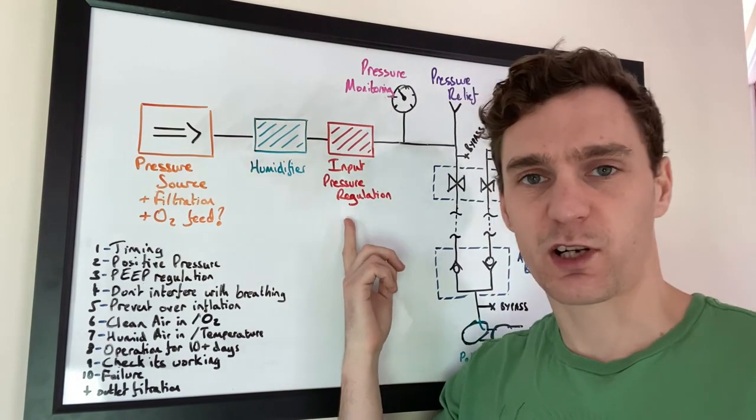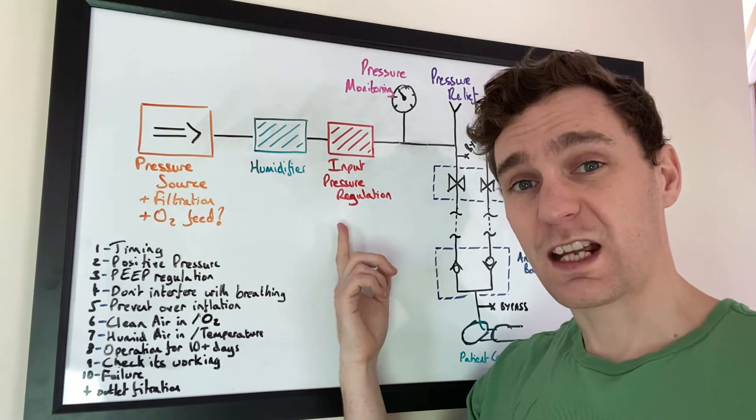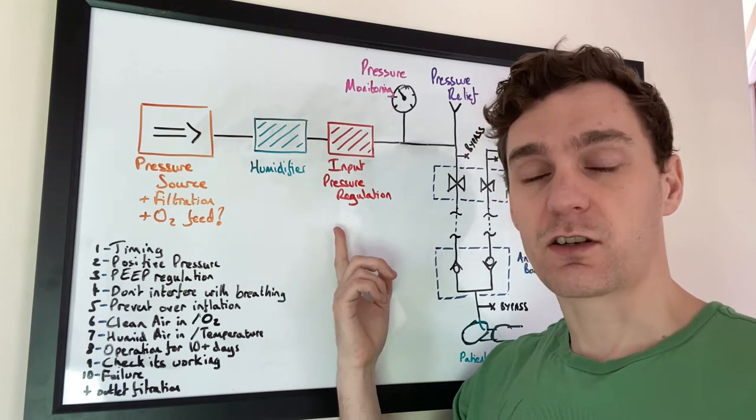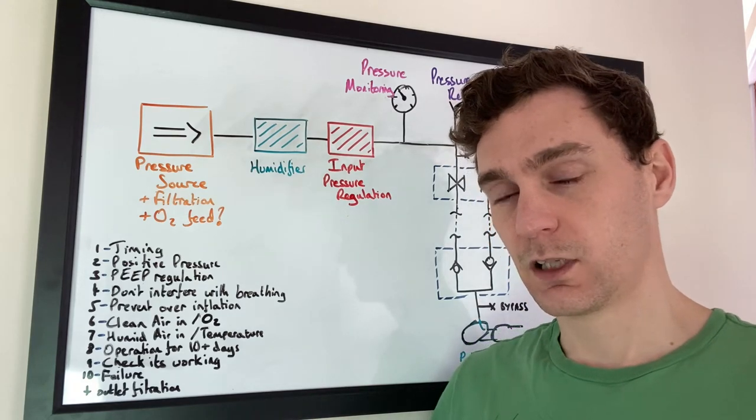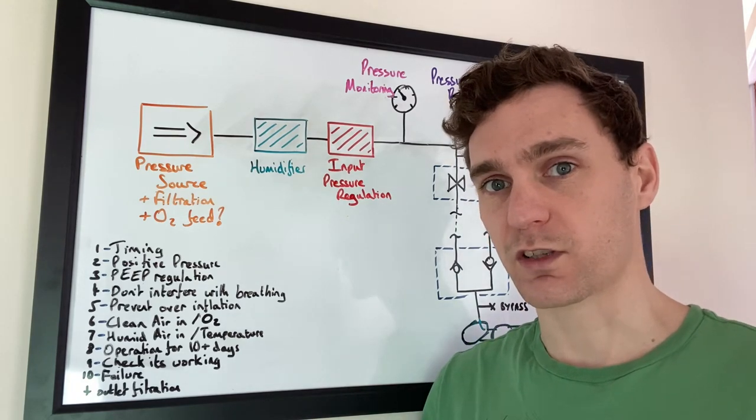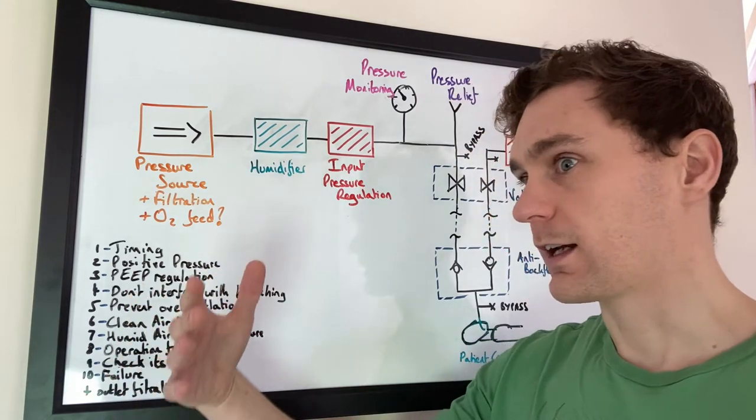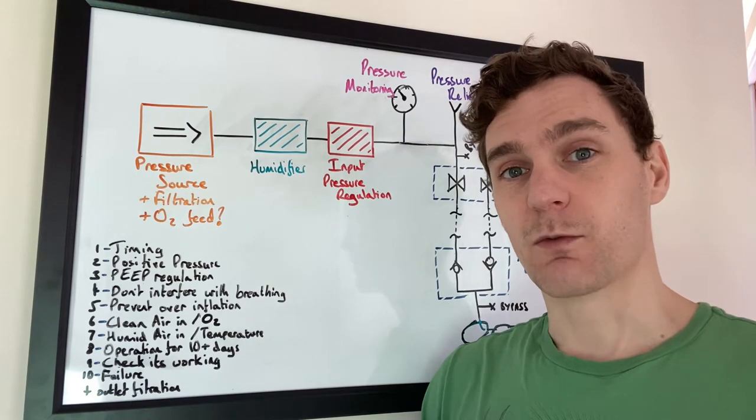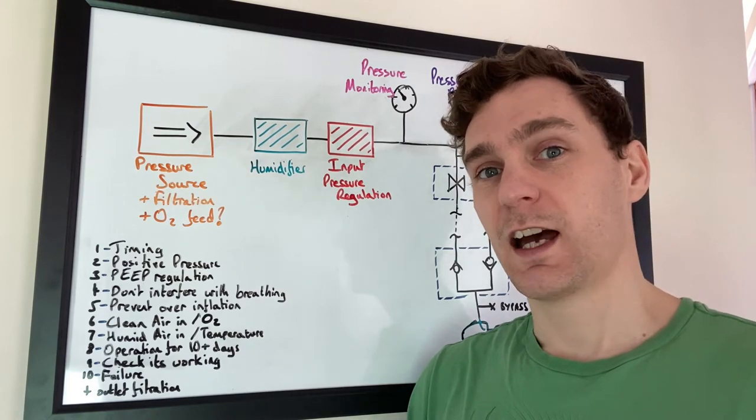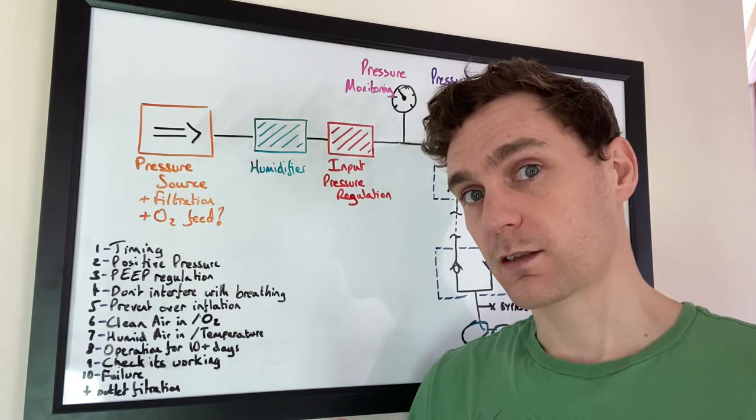Next on the list is input pressure regulation. This is important not only to be able to set it but to be able to change it over time. This is because the needs of a patient might change over time. You might start with a high pressure when you want to have a large volume of air going into their lungs. But then at a later date if their lung function begins to be impaired, you might want to have a lower pressure and a faster breathing rate. So shorter shallower breaths rather than long deep breaths.